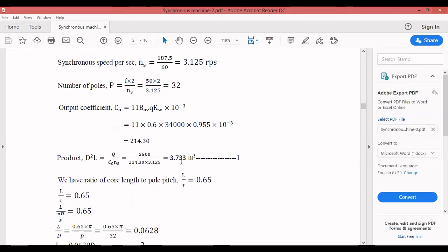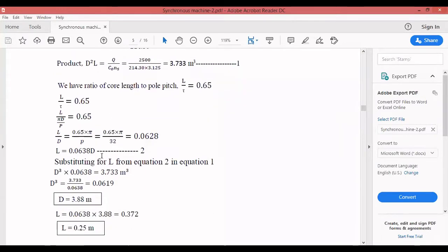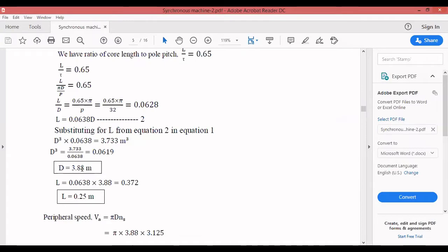Using the condition L/τ = 0.65 for circular poles, we derive L = 0.0638D (Equation 2). Substituting into D²L = 3.733 gives D ≈ 3.88 m and L ≈ 0.25 m.